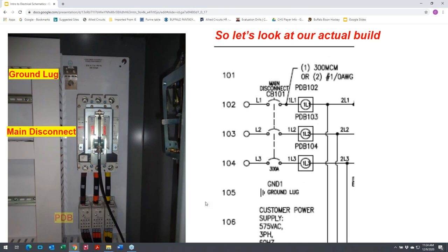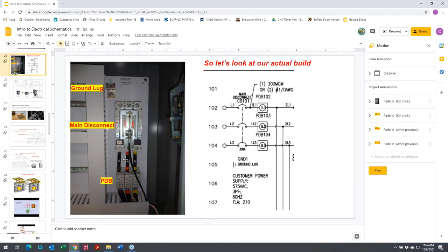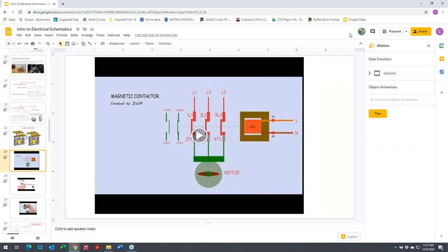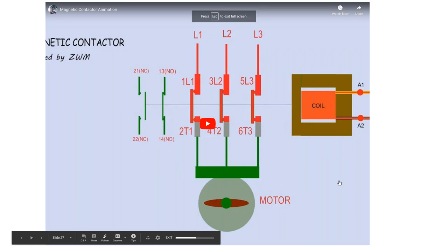Carl added: the brown, orange, and yellow color scheme — per NEC code — references 480-volt power going through those wires. An easy way to remember it: 'BOY' — the first letter of Brown, Orange, Yellow — represents the three phases of a 480V system.